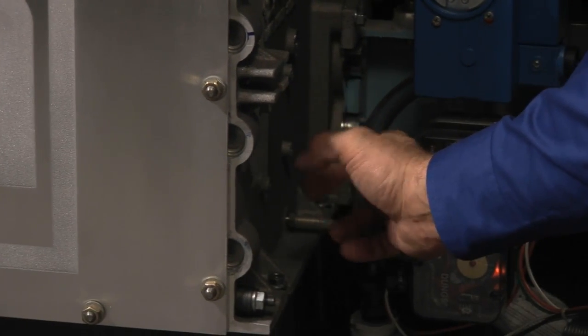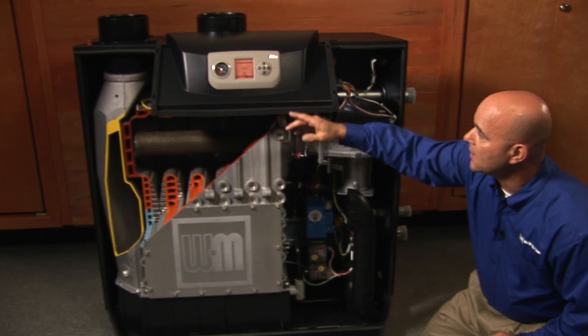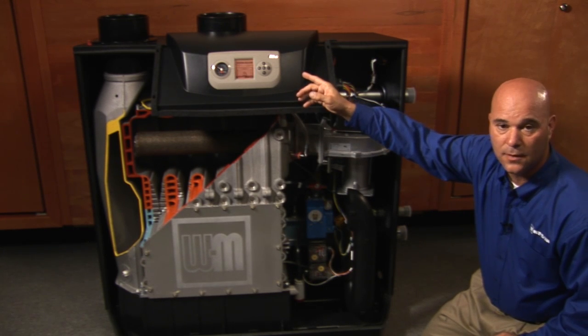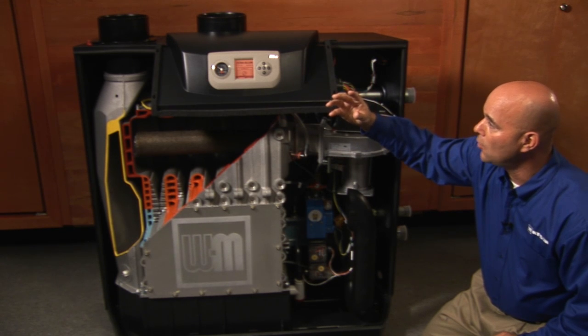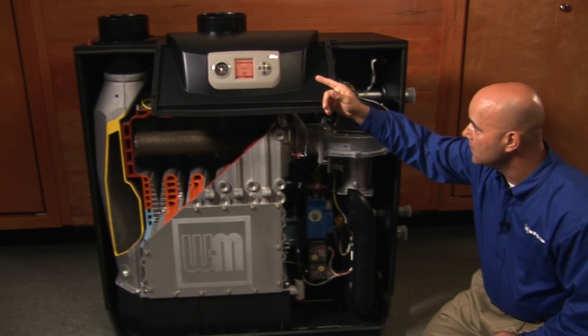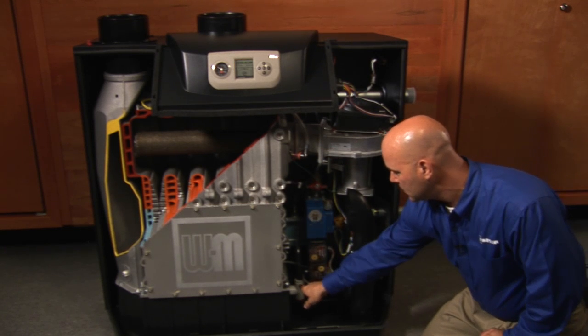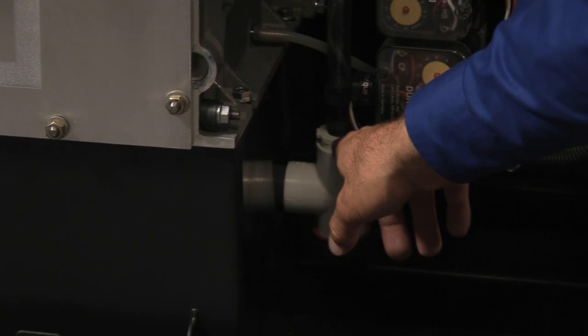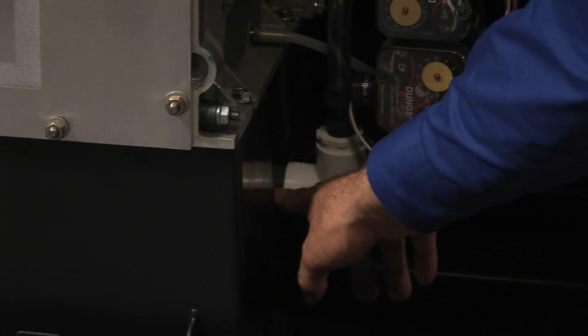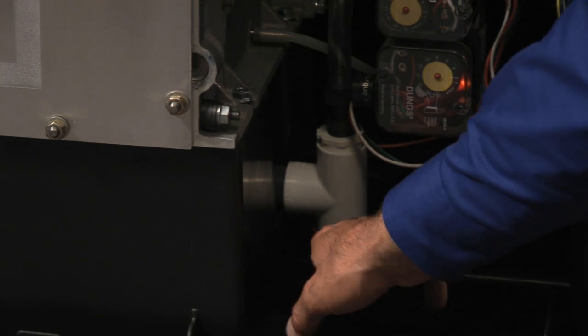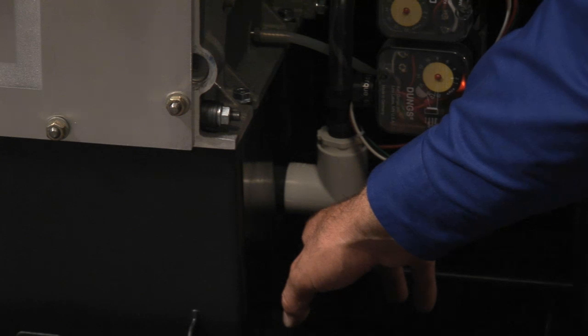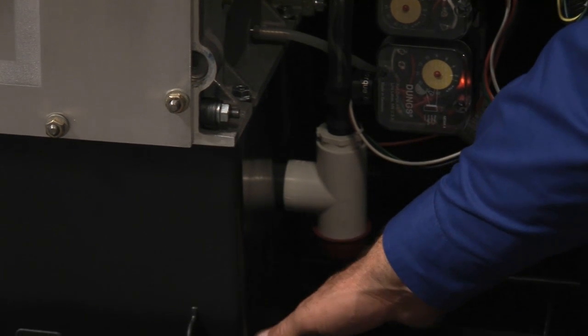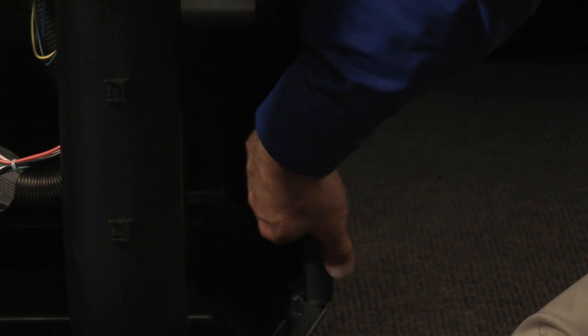Coming around, you'll see this clear tube. This clear tube goes all the way up around the heat exchanger and ties into the exhaust port. So any condensation that runs back to the boiler will get caught in the rain trough, and it will run down and tie into the condensate trap. The condensate trap mounts directly into the base of the boiler, and then there's a clear tube that comes off of the bottom. This red cap gets removed. We have a clear tube that comes off, drops down, comes up and out through the side of the jacket. And we give you all the PVC fittings you need and the clear tube to get you outside of the jacketed area.